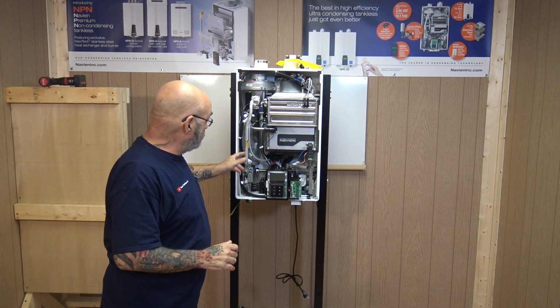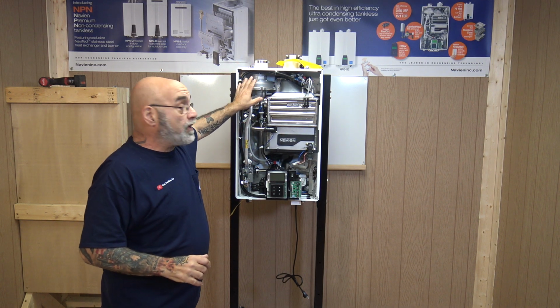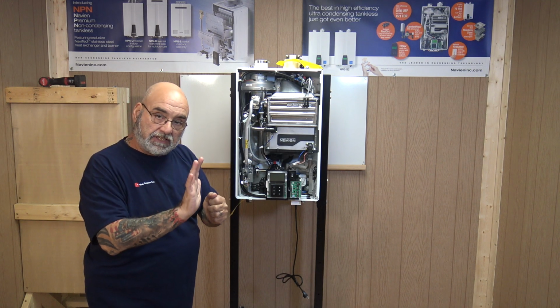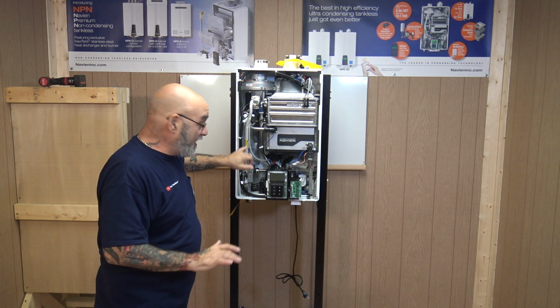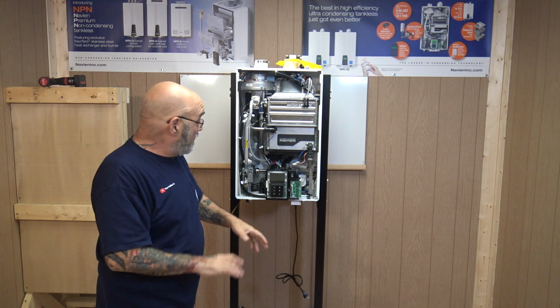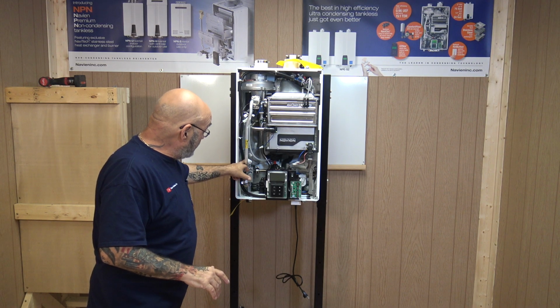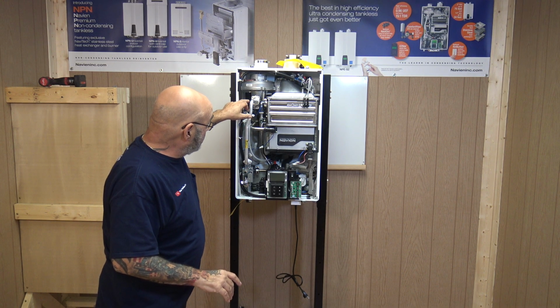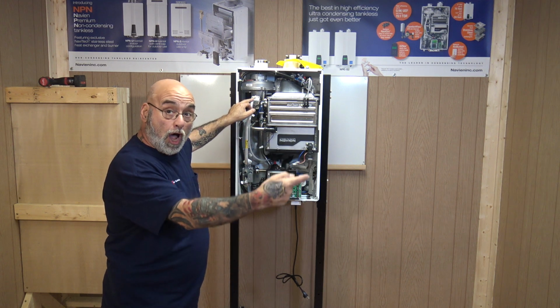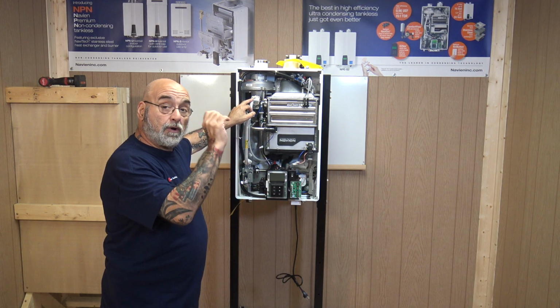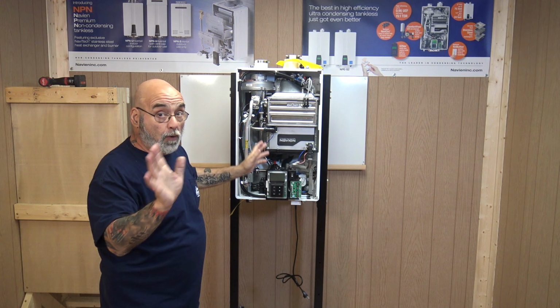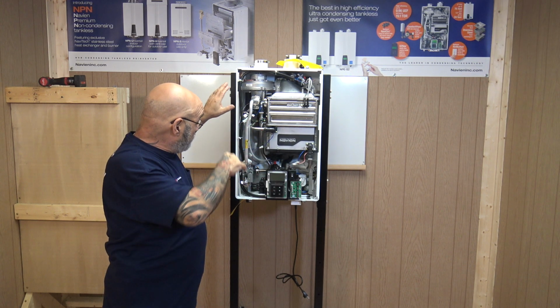4 screws, 2 screws, put it up. Oh, when you take it down, I always take a nice clean rag and wipe off the 2 faces to make sure nothing is on it. Just make sure your O-ring is here, your main O-ring is there, your figure 8 is the one behind the orifice, and the orifice is one direction - it'll only go in one way. And then you put it in.